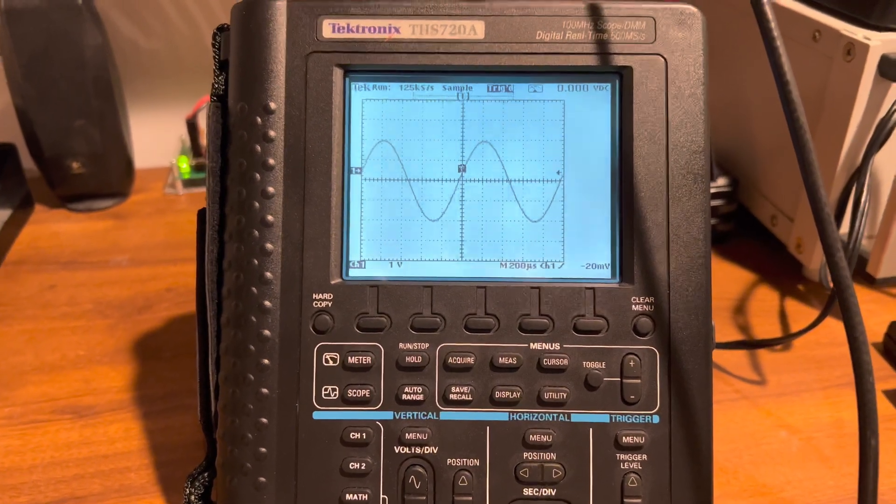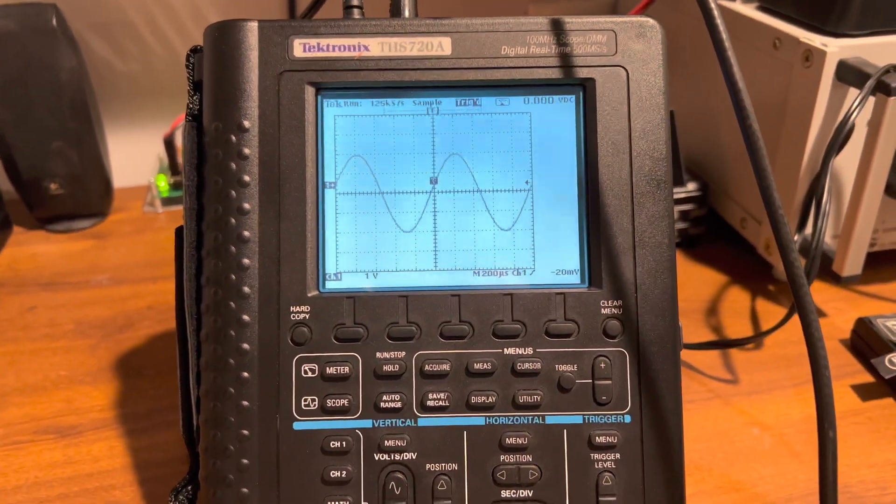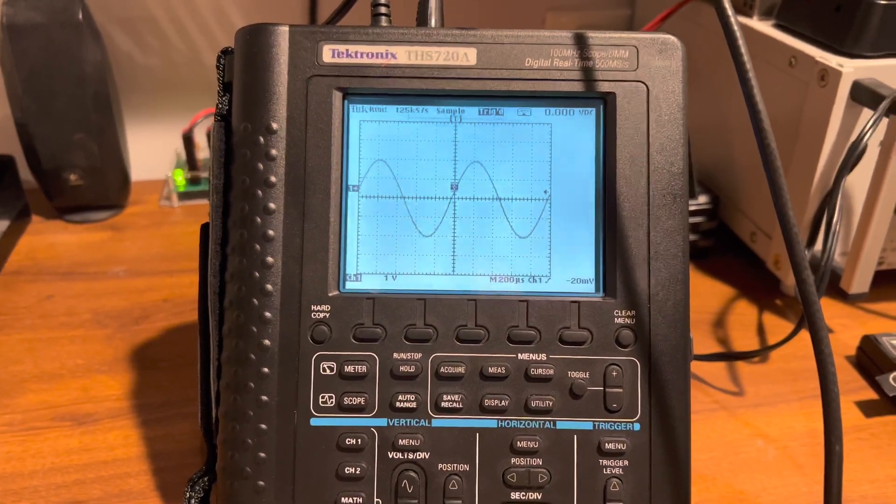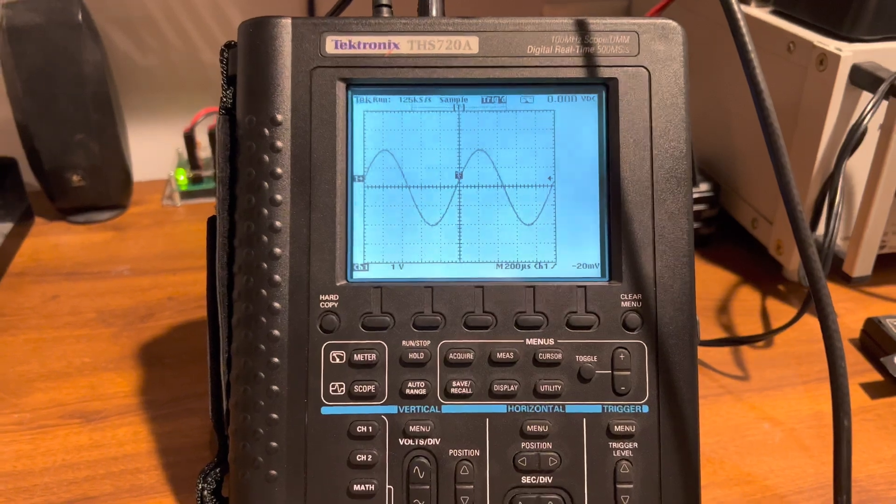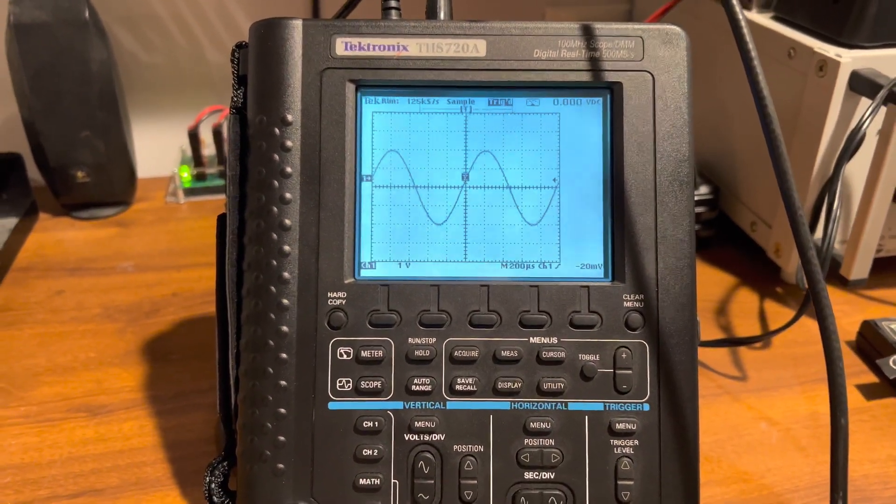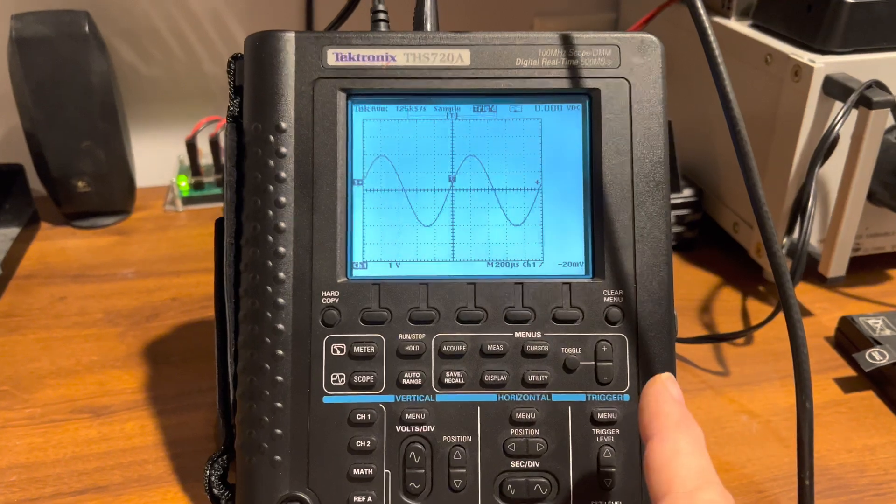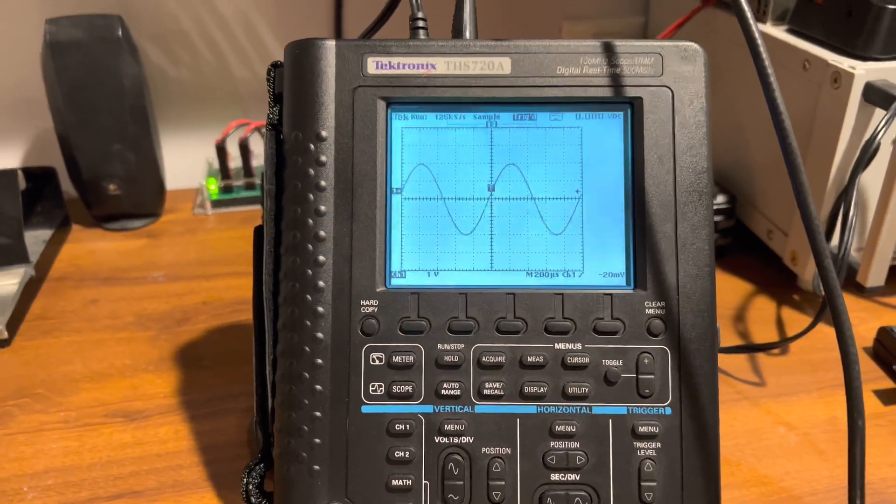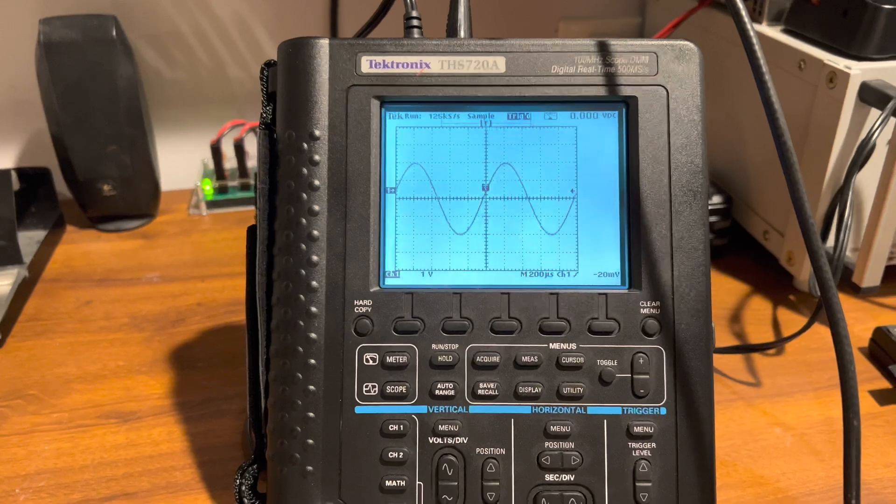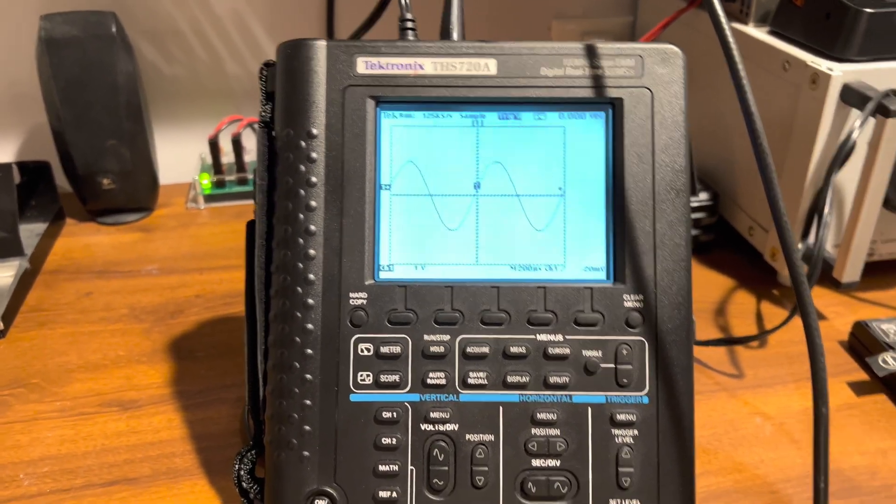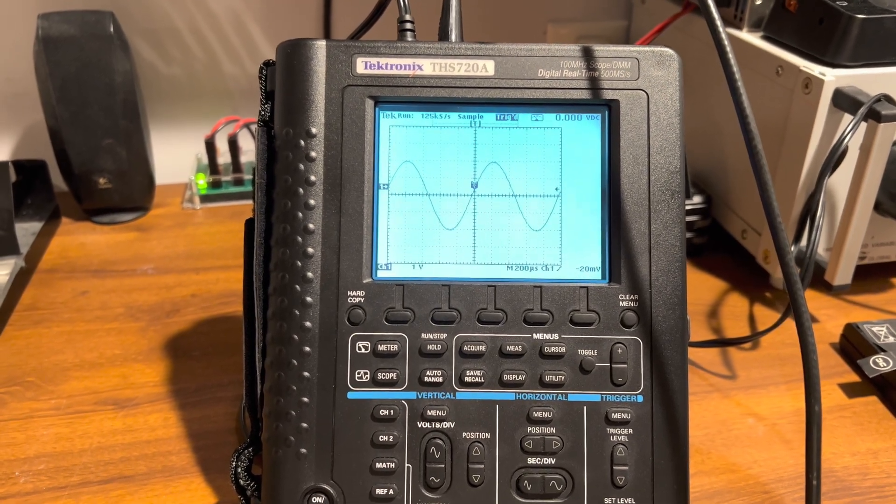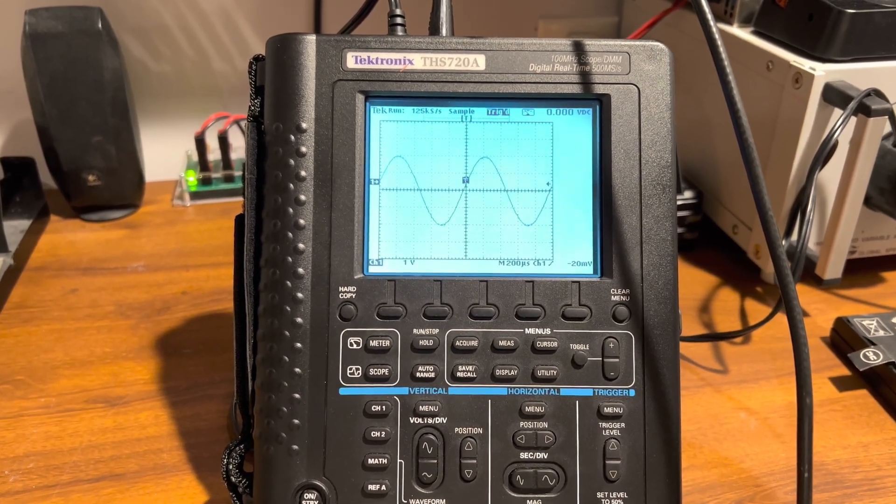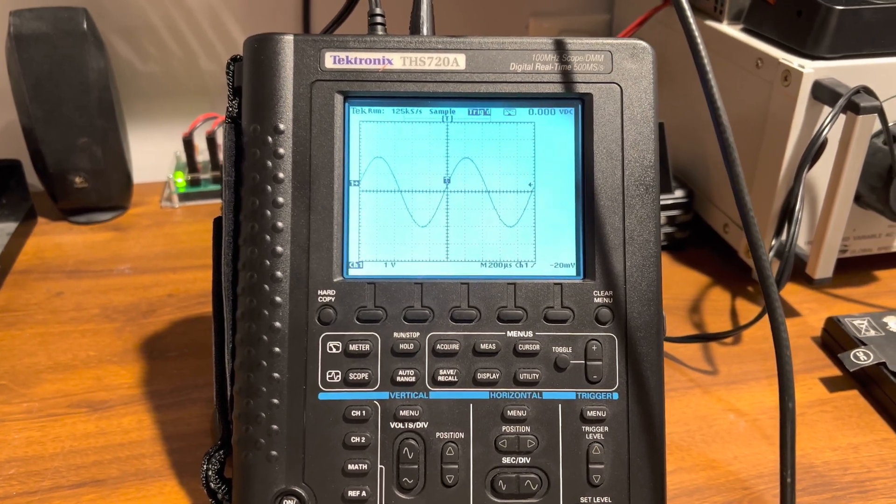Whatever that offset is, it's likely the optic couplers because as they age they do cause that, or it could be the relays themselves. I used to repair these—it's not actual SMD capacitors because there's only two in this thing and it's on the multimeter side, it's not on the oscilloscope side. So it's not capacitors, it's likely those optic couplers or those relays because it's been sitting so they could have oxidated, causing that.